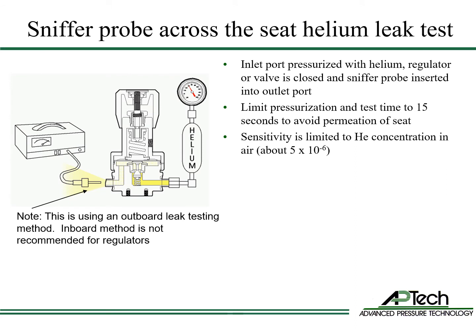The sniffer probe across-the-seat helium leak test method pressurizes a valve or regulator's inlet with helium, and the operator inserts the sniffer probe in the outlet. As mentioned previously, helium permeates the seat material, so test time should be limited to 15 seconds. This test sensitivity is limited to the helium concentration in air, about 5×10⁻⁶.